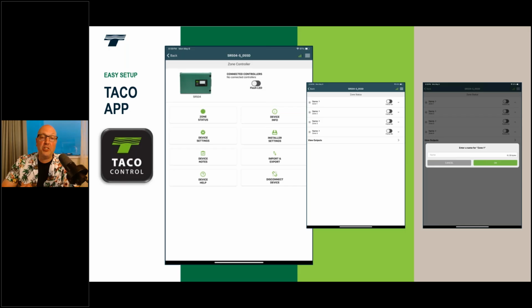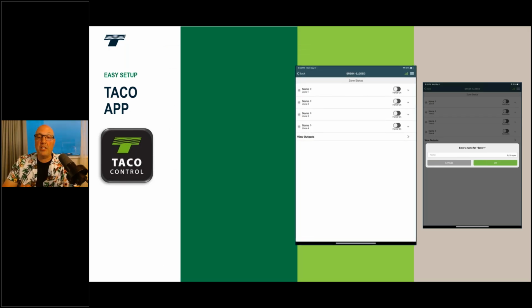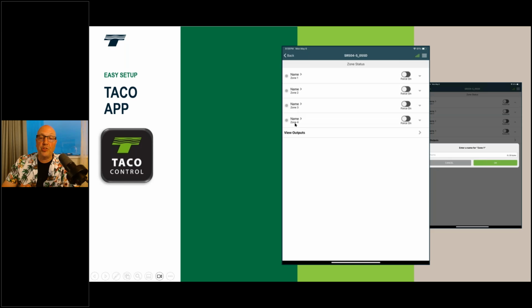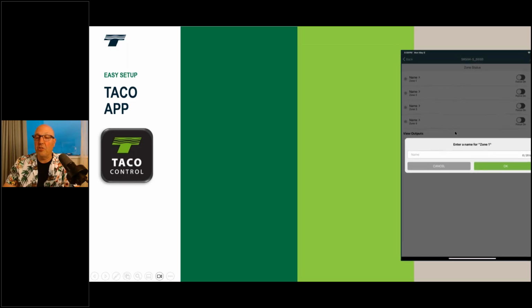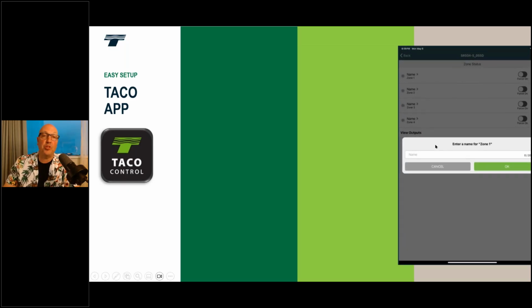So if I were to click on zone status, as we zoom into that, you'll see each one of the zones that the control has. You can name them, but this part I really like. You want to check your wiring. You want to make sure you did it right. Rather than running up and down the stairs to turn a thermostat on and off, you can just click force on right here, and it's going to turn your pump on. So you don't have to get out your STS, right? Your sophisticated thermostat simulators. You can just click it right here and the zone's going to turn on, okay? And then you can see here how we go ahead and name those zones.